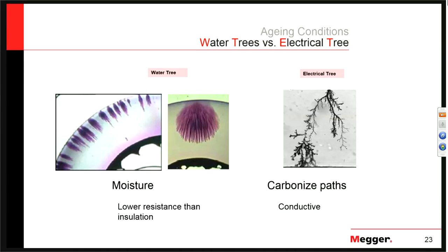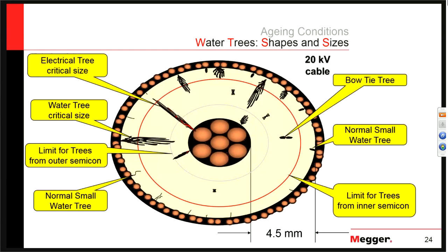The conductivity of electrical trees comes from carbon on the outer edges of the channel. Once the electrical tree bridges enough of the insulation, the cable faults and we have to go repair it. Water trees take a very long time to grow — 5, 10, 20 years. But electrical trees, once they form, will fail a cable in a number of hours. When a water tree grows to a critical size, it's in danger of growing an electrical tree at any moment, causing failure.